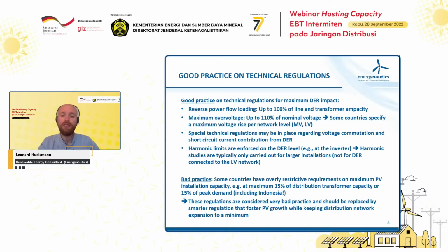Including Indonesia, we see a number of countries that have such a limit in place, limiting the amount of PV to 15% of distribution transformer capacity, or limiting it to 15% of peak demand. However, this was actually a practice that, to my knowledge, originated in the US around 25 years ago, and they already removed this regulation and improved it about 20 years ago.